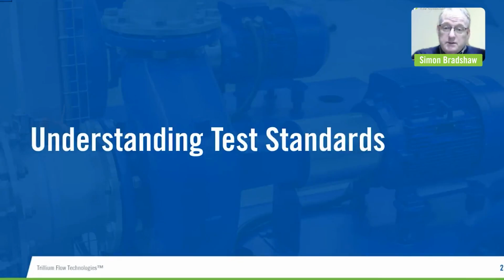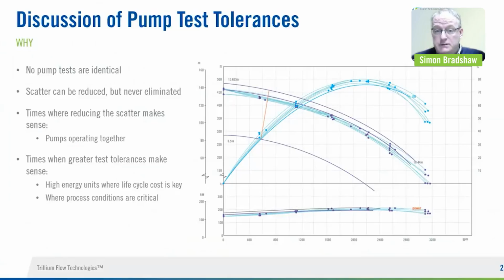All right, thanks, Massimiliano. So we're going to talk a little bit now about, go a little bit deeper into the test standards and try and highlight certain key things that you should really pay attention to. So next slide. So we talked about this earlier, that pumps are not digital machines. No pump test is identical. You can, with certain manufacturing controls, reduce the scatter that you get, but you can never eliminate it. That's just the nature of manufacturing.